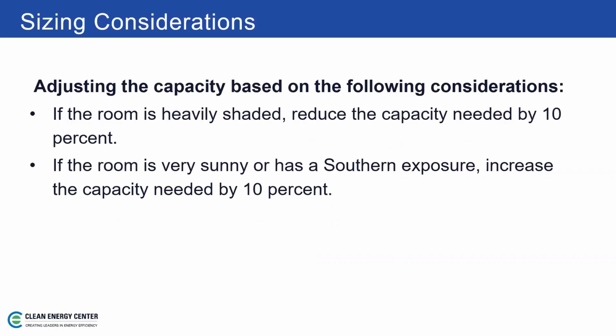There are some rules of thumb for adjusting capacity based on a couple of considerations. If the room is heavily shaded, well insulated, maybe has low E glass, you might want to reduce the capacity a little bit, as much as by 10%, which isn't going to have a huge impact, but it's a consideration. And if it's very sunny, maybe it's on southern exposure, no shades, no blinds, you might want to increase that capacity by about 10%.